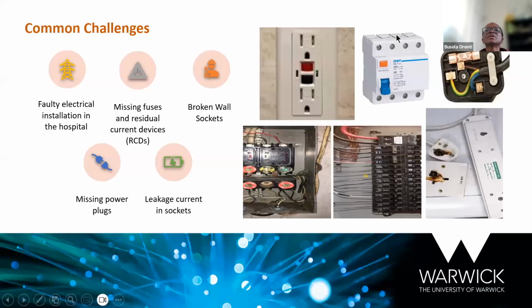So some of the common challenges, as said, in a regular environment, you'll probably find faulty electrical installation in hospitals. You have missing fuses and residual current devices, I mean, circuit breakers generally. You have broken wall sockets, sometimes missing power plugs, leakage current in sockets. I worked in a lab when I was in Nigeria, an electrical lab. Your live and neutral are not supposed to read anything when you put your meter in. You're not supposed to have any leakage current, but all the sockets were reading from one to another, which is a problem. And we've seen this in other African countries too.